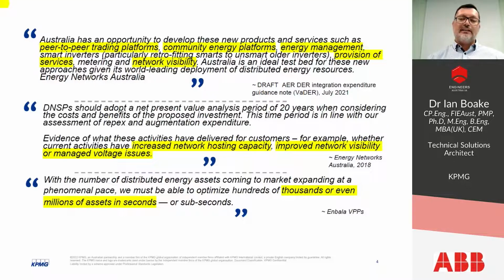The Energy Networks Australia, or ENA as they're called, started this journey probably in 2018 with their DER roadmap, and they themselves recognise the importance of the grid as the central connection point, almost like an internet connection for power. But there's a need for hosting capacity analysis, and for that, in some instances, to be increased, where the local network doesn't offer sufficient capacity for all of the DER that's been connected to that network to be injected back into the network. Again, they've also identified the need for network visibility, and very, very importantly, to manage the voltage issues, because there's a range within which consumer appliances need to be operated without deleterious damage to that equipment. So they picked up on network visibility as well as managing the voltage issues.